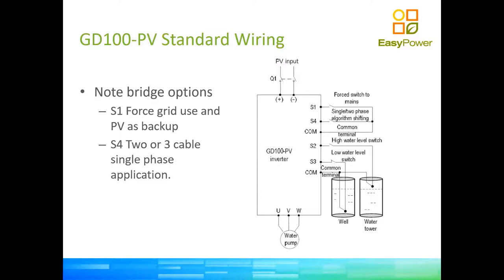S1 and S4 serve two specific functions. S1 tells the inverter to use PV as backup — by connecting S1 to common with a bridge, you can disable the function that makes solar the priority. S4 tells the inverter whether the pump uses a two-wire or three-wire startup configuration. Some single-phase pumps require a three-wire setup to start, and for those you need to wire S4 to common.